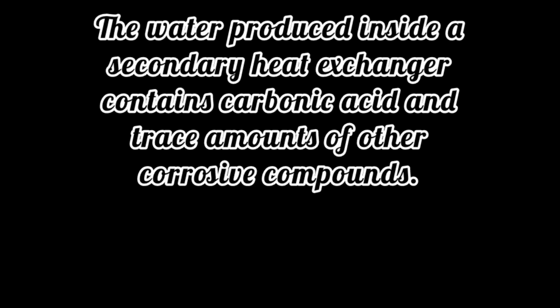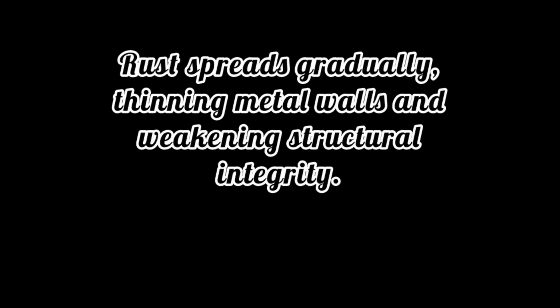Step 3. Acidic condensate and metal degradation. The water produced inside a secondary heat exchanger contains carbonic acid and trace amounts of other corrosive compounds. These acids attack protective coatings and metal surfaces from the inside out. Once corrosion begins, it does not stop on its own. Rust spreads gradually, thinning metal walls and weakening structural integrity. As metal weakens, it becomes more susceptible to cracking due to thermal stress. This process happens slowly and silently, often without obvious symptoms, until the damage is already advanced.